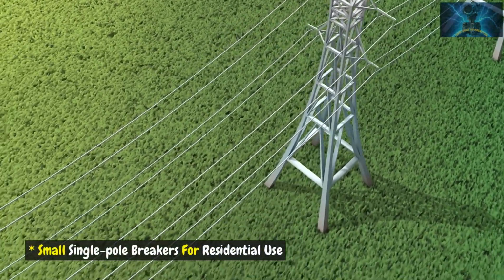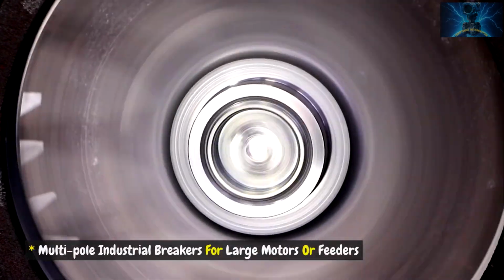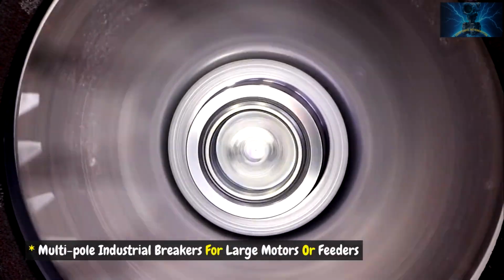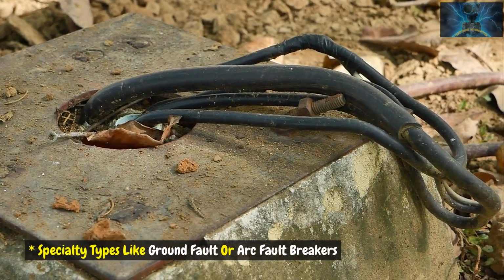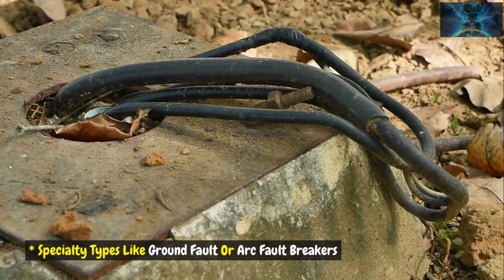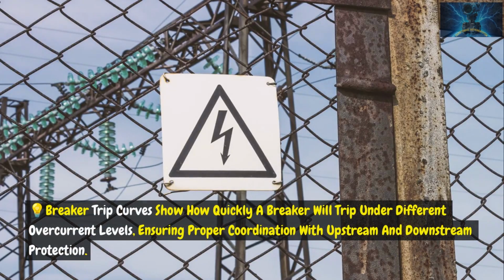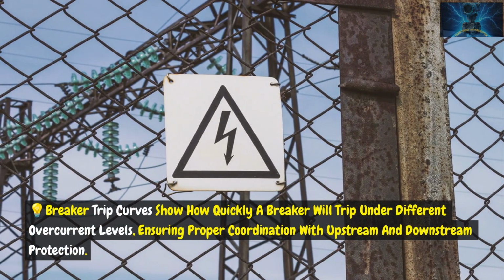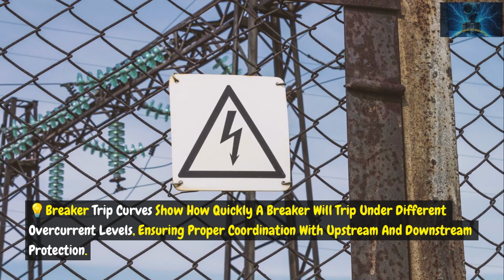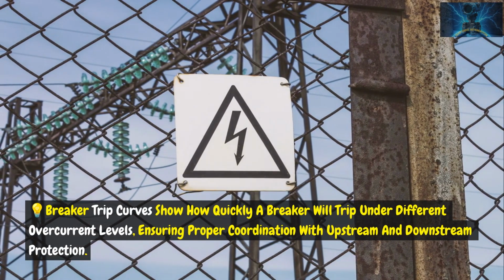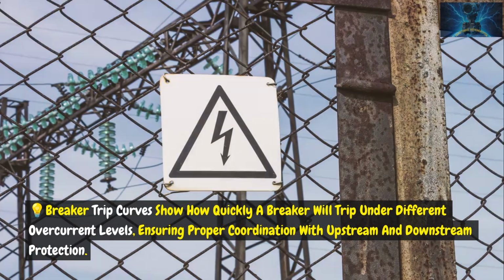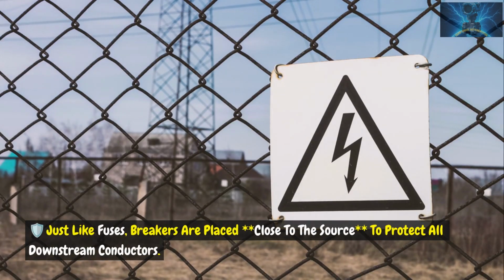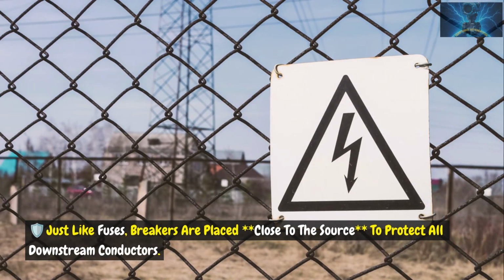Small single-pole breakers for residential use. Multi-pole industrial breakers for large motors or feeders. Specialty types like ground fault or arc fault breakers. Breaker trip curves show how quickly a breaker will trip under different overcurrent levels, ensuring proper coordination with upstream and downstream protection. Just like fuses, breakers are placed close to the source to protect all downstream conductors.